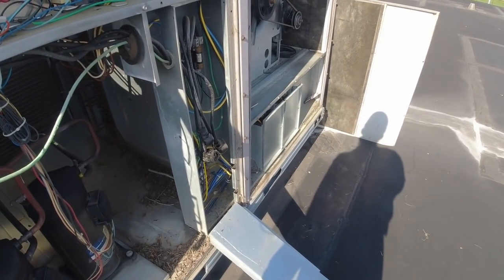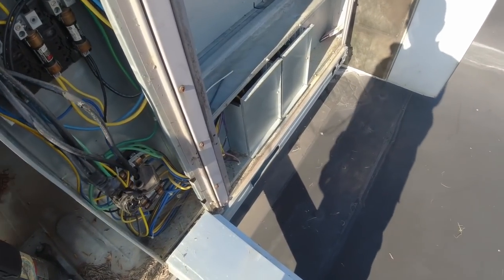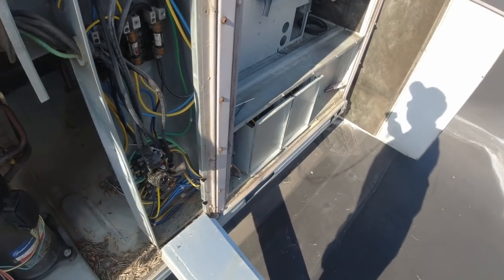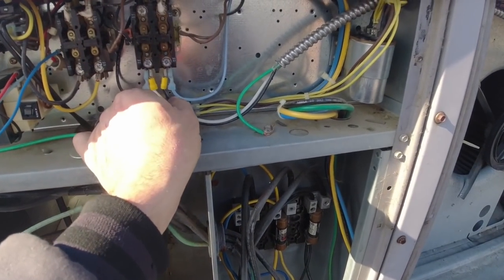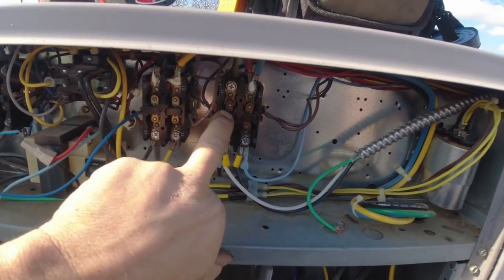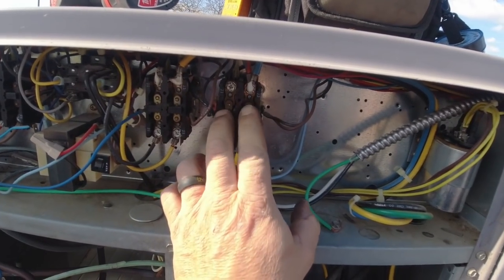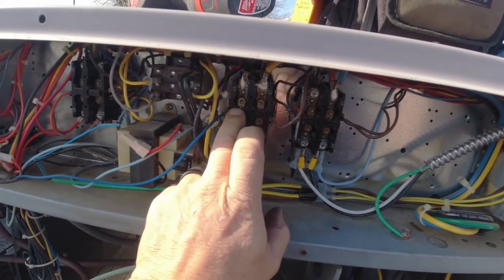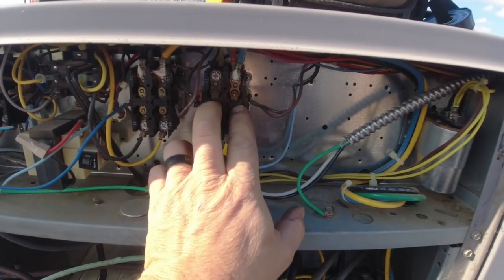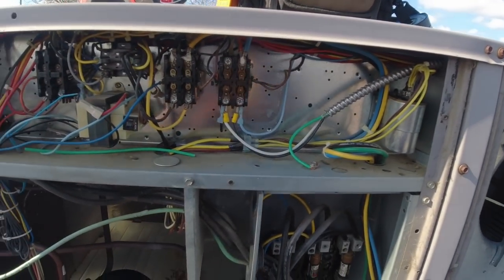Yes, the strips are being shut off at the same time, but these are relays for these strips. They're not thermal discs that bring them on. So I'm not too concerned, because that's how it shuts off normally. Power's back off again. I mean, if you push on the edge, it doesn't go in. Push on that side, it does. It's not worth it to me. That one goes in. That one doesn't. It's easy. I mean, in theory, yeah, it's probably not... I don't know. I'm just not taking a chance. Let's go ahead and get that contactor replaced.